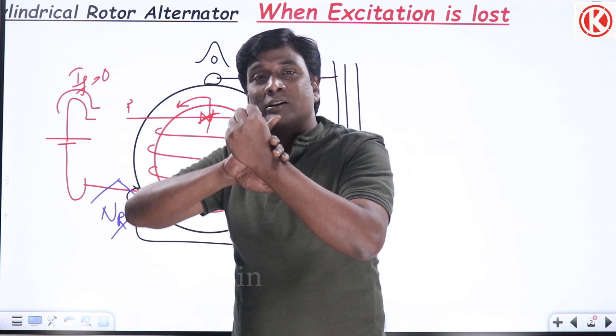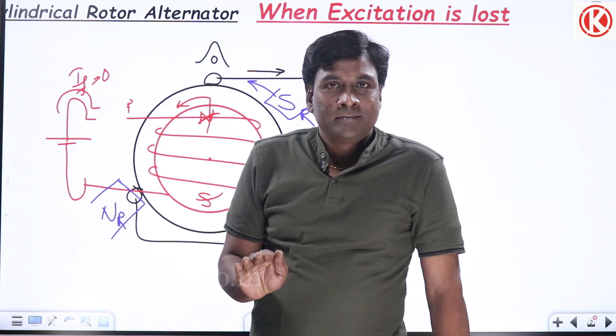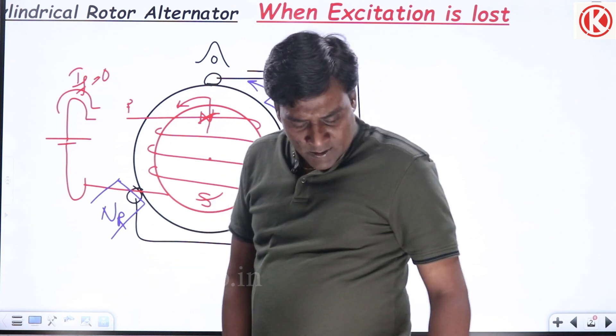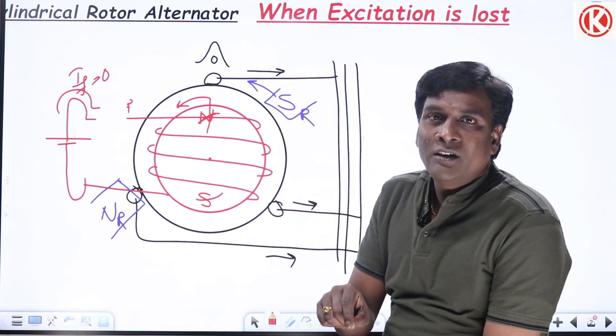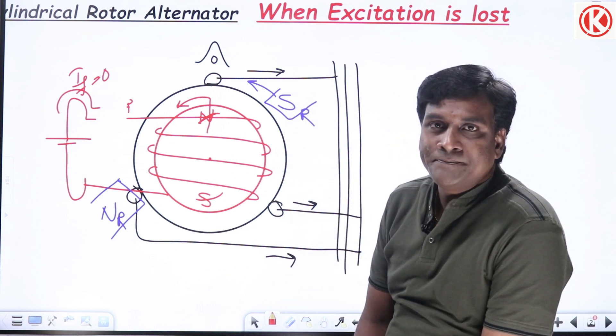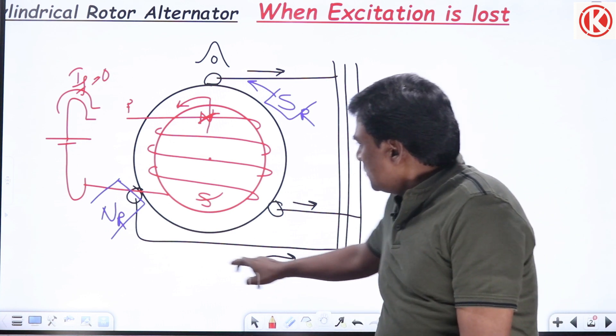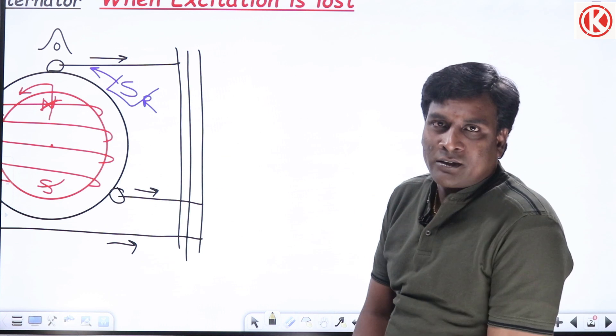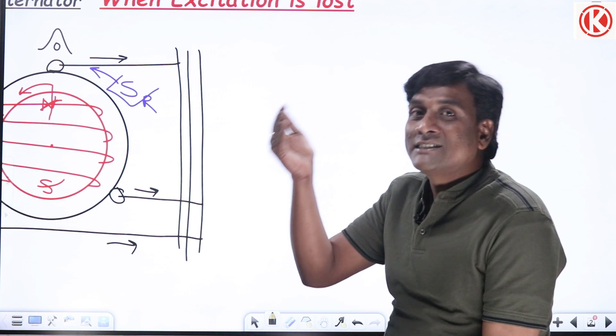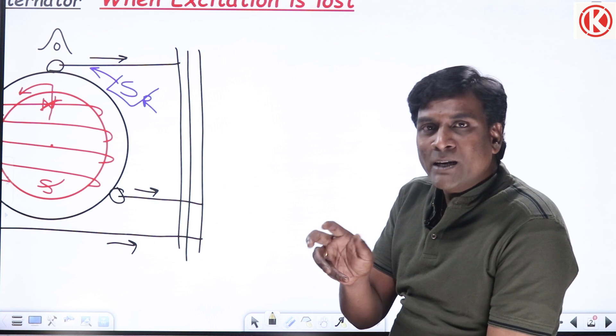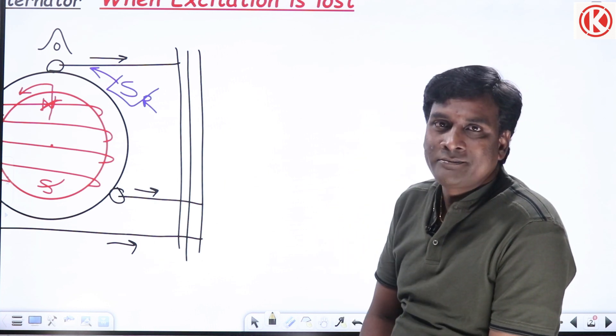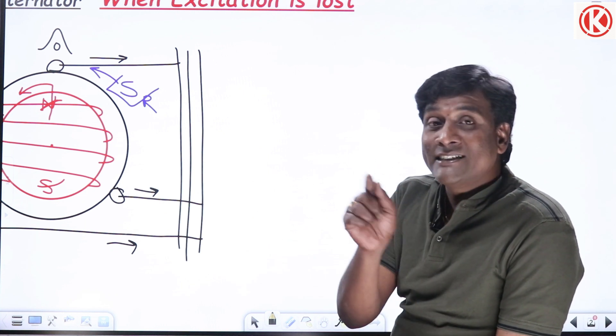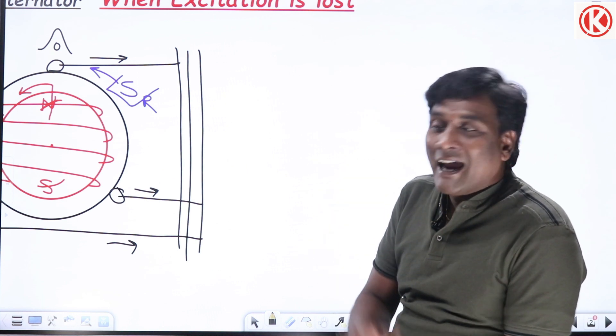Once the poles disappear, prime mover power input is there but back torque is not there, so the rotor will accelerate. The over-speeding relay in the alternator will recognize this fault and give a signal to open the circuit. Now, the idea that any rotor rotating above synchronous speed automatically becomes an induction generator is wrong. There are two basic conditions: the number of poles of the stator and rotor must be the same, and the stator and rotor MMFs must be stationary in space with a non-zero angular displacement.